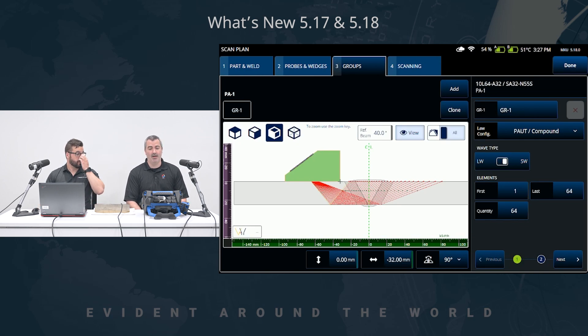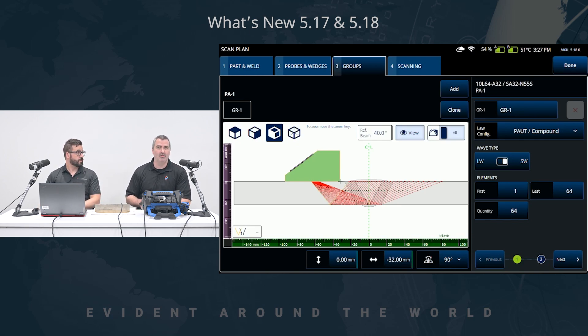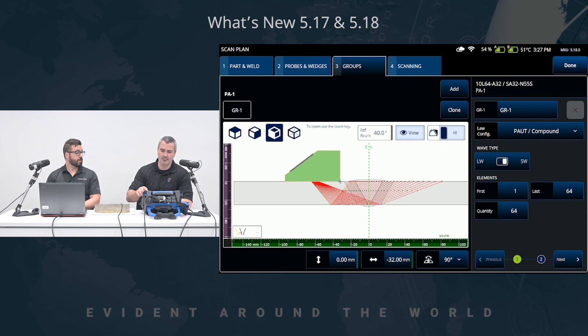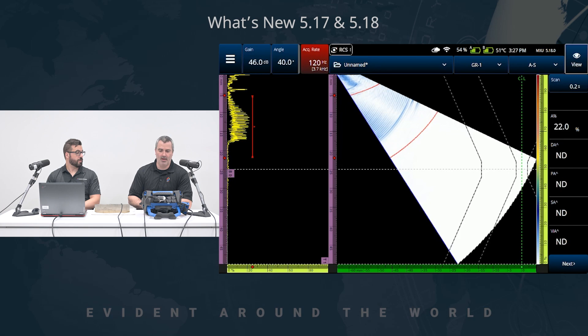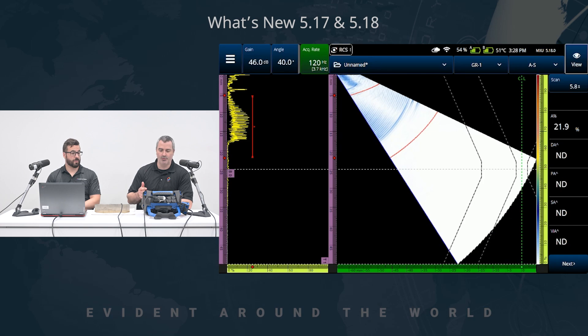So on my side of things, we have the OmniScan X3. As you can see, I'm currently in the scan plan with just a generic one inch or 25 millimeter V-weld using a compound scan. And as I exit or accept the scan plan, we end up with this layout. Default range of 50 millimeters, way outside of the overlay.